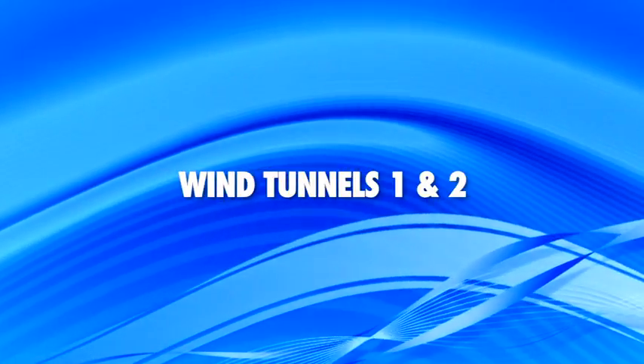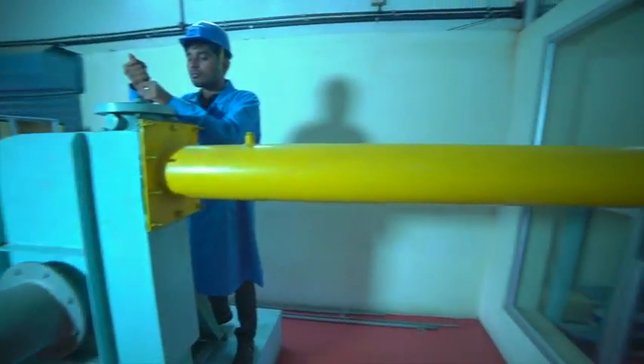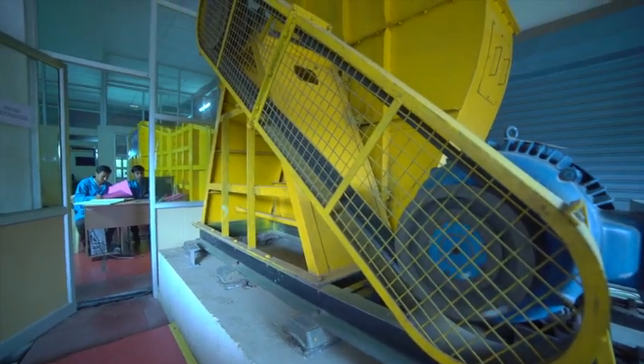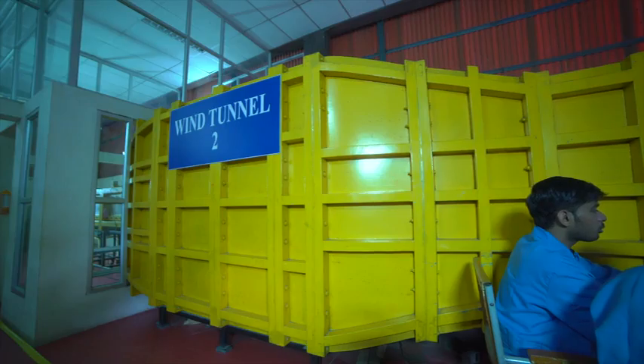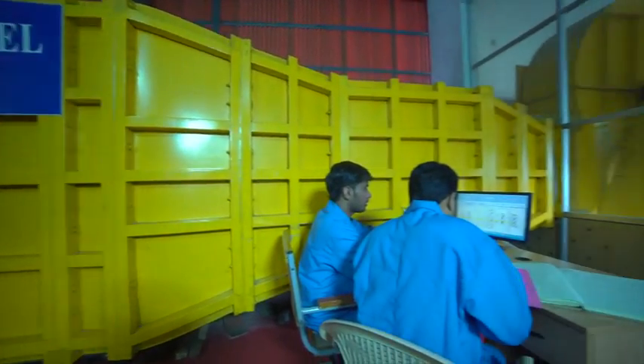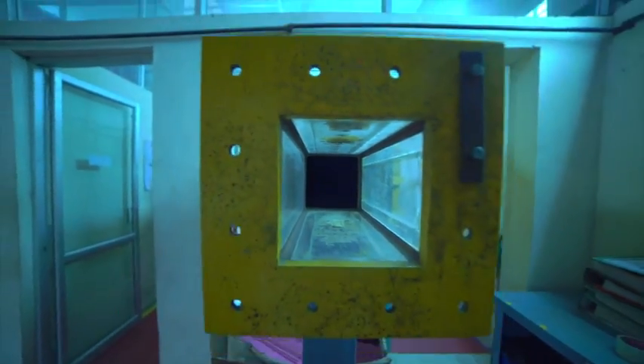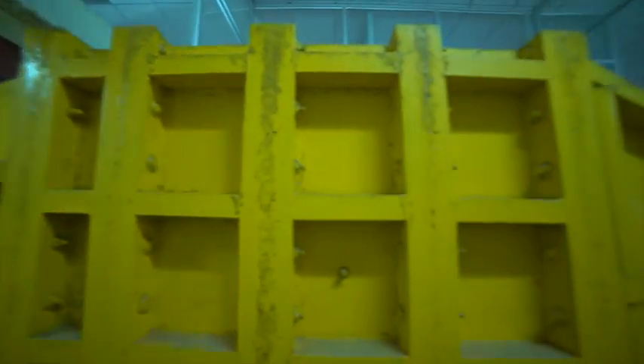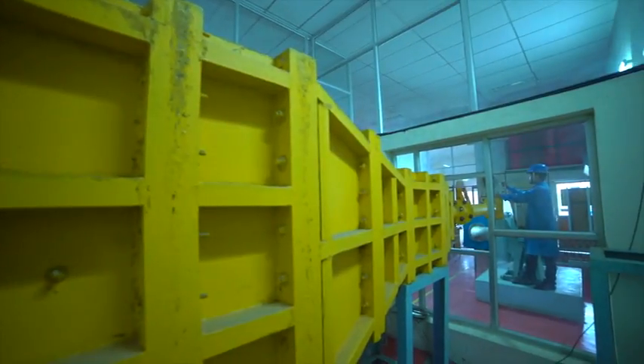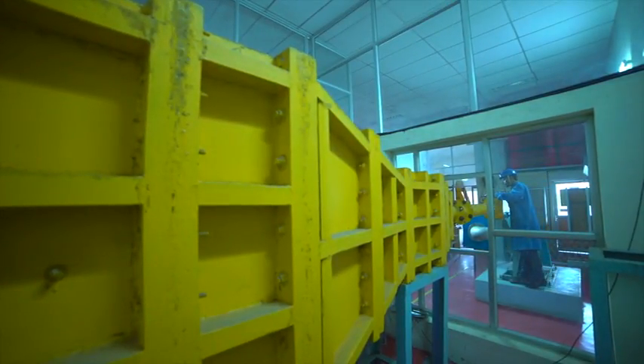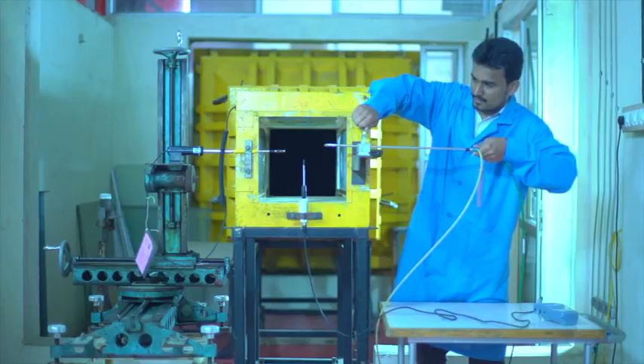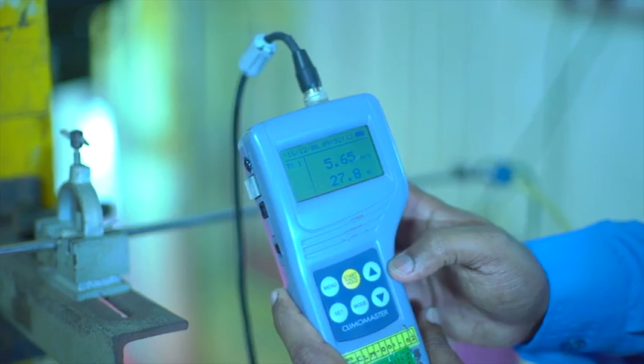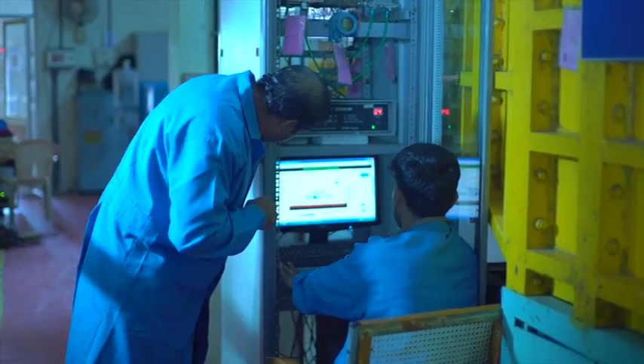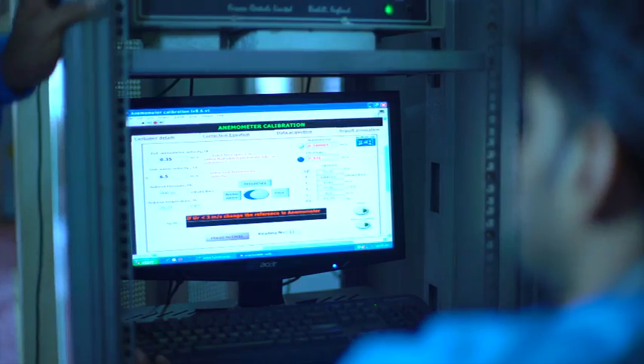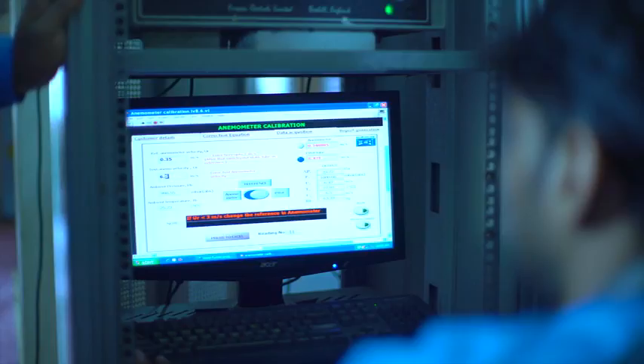The wind tunnels 1 and 2 help in calibration of different types of anemometers, pitot tubes, velocity probes, aerofoil, etc. This facility is vitally utilized by user industry. FCRI can calibrate and also test items at air speeds up to 80 meters per second. In addition, the lab undertakes measurement of air or gas in large ducts at site for power, petrochemical and process industries using traversing method.